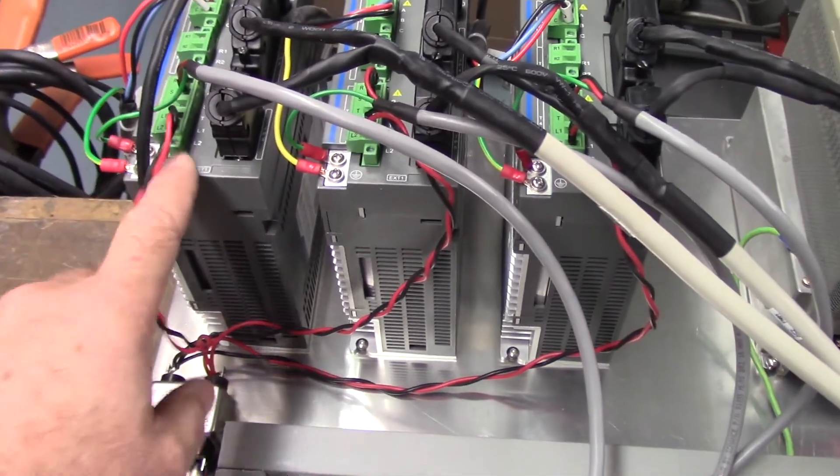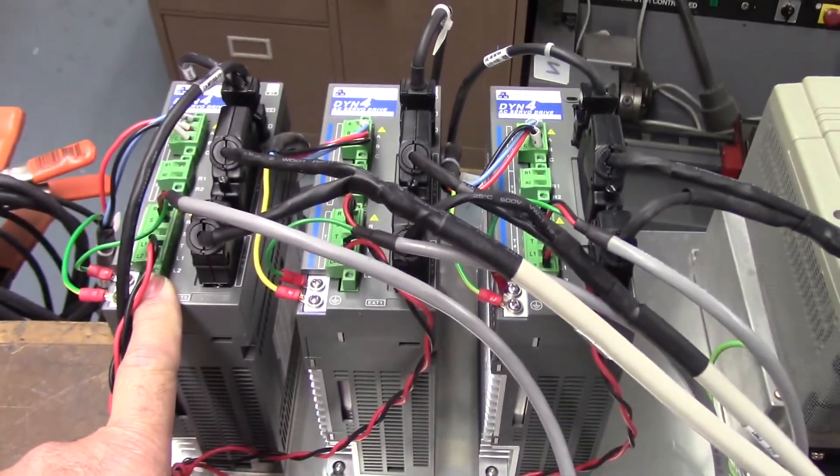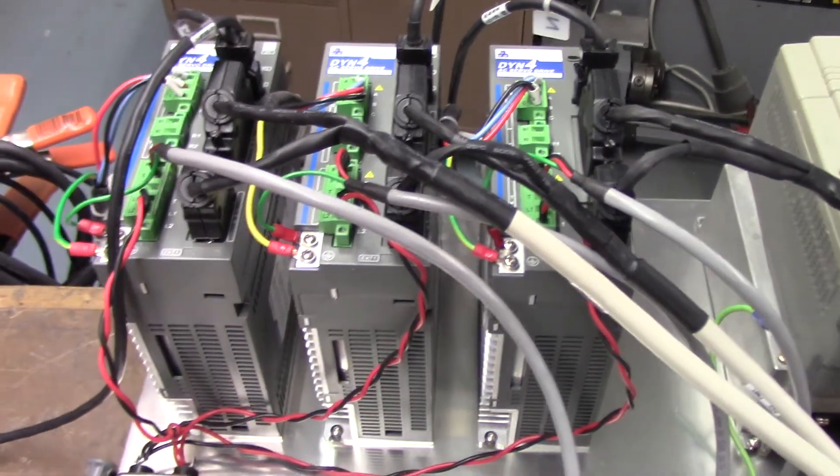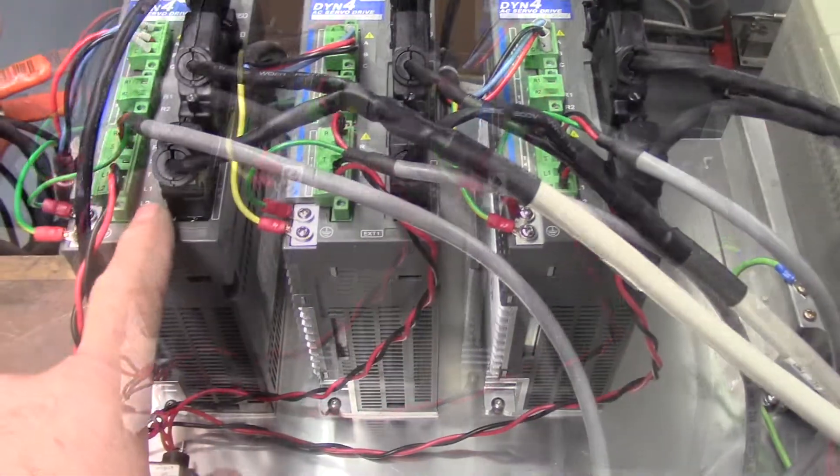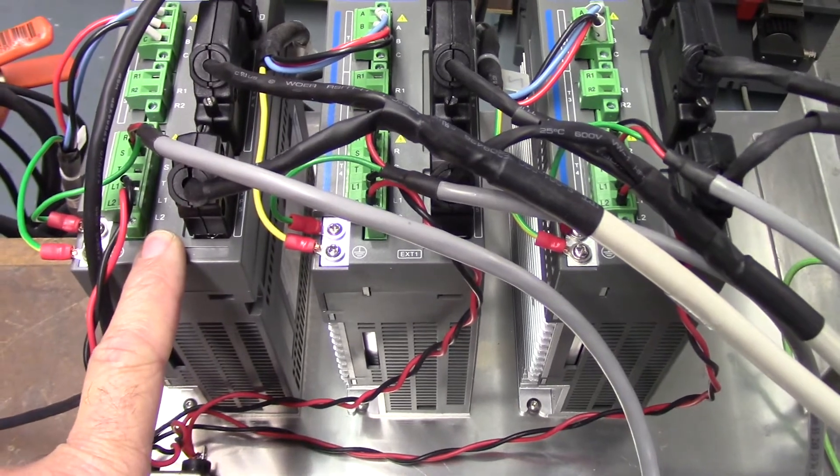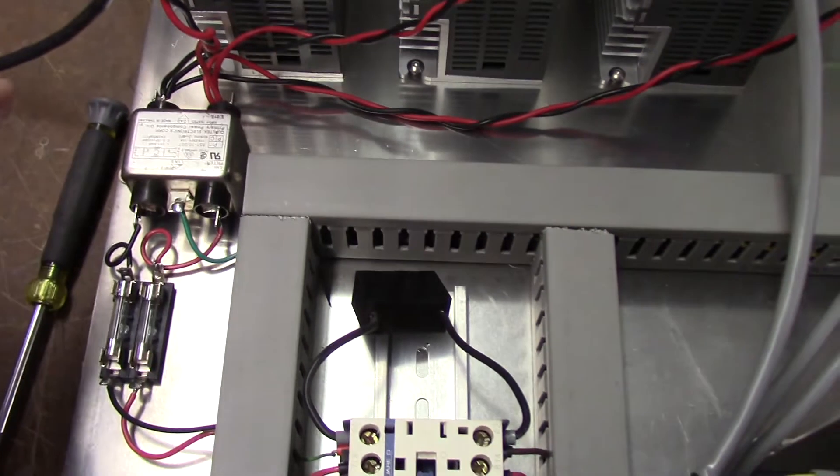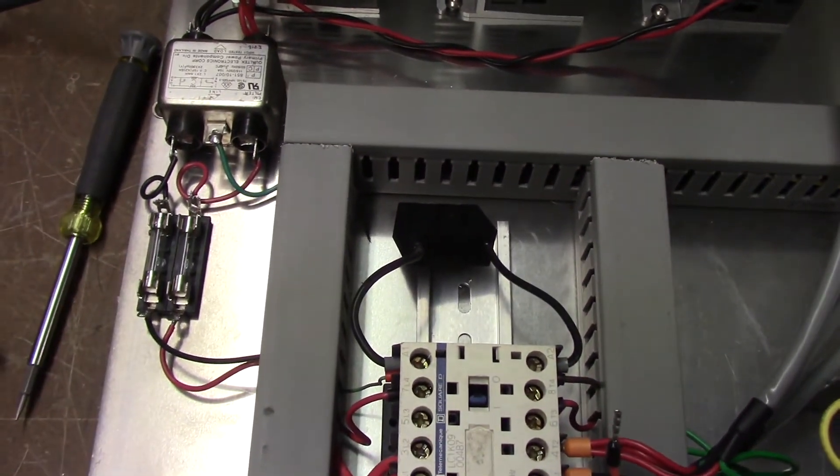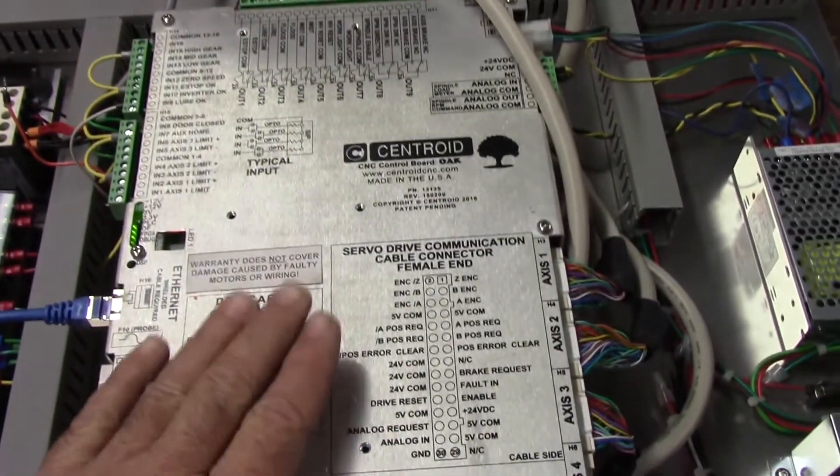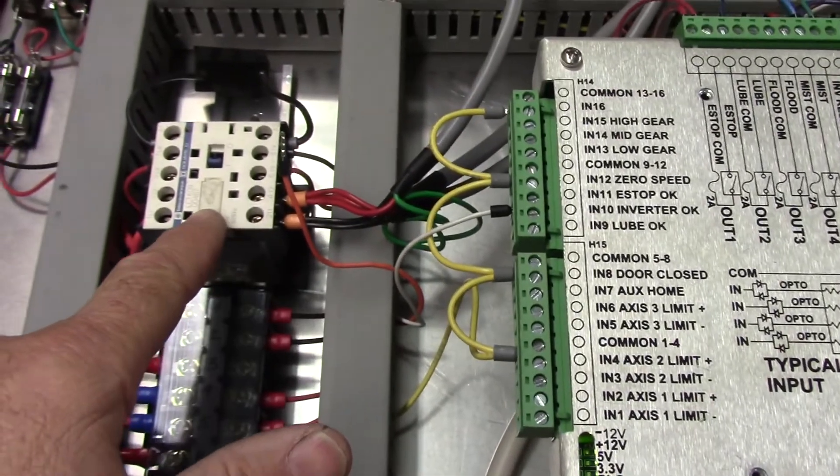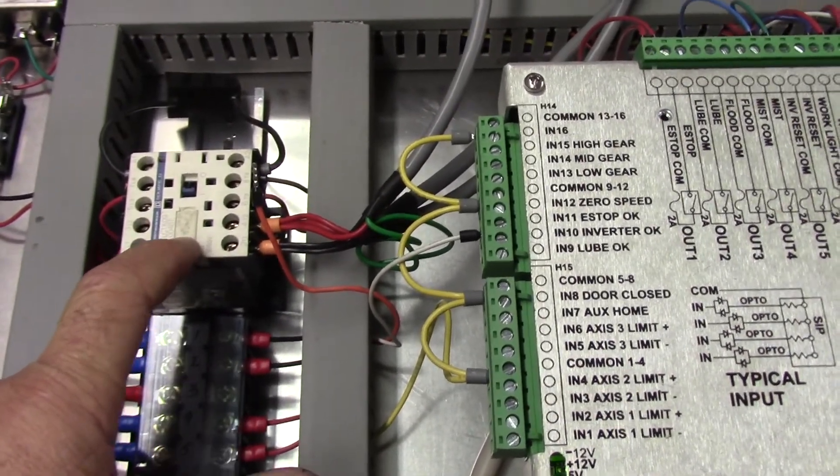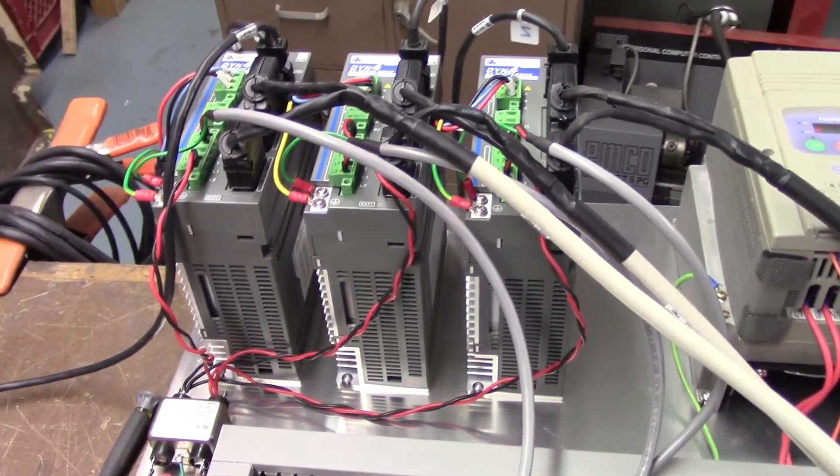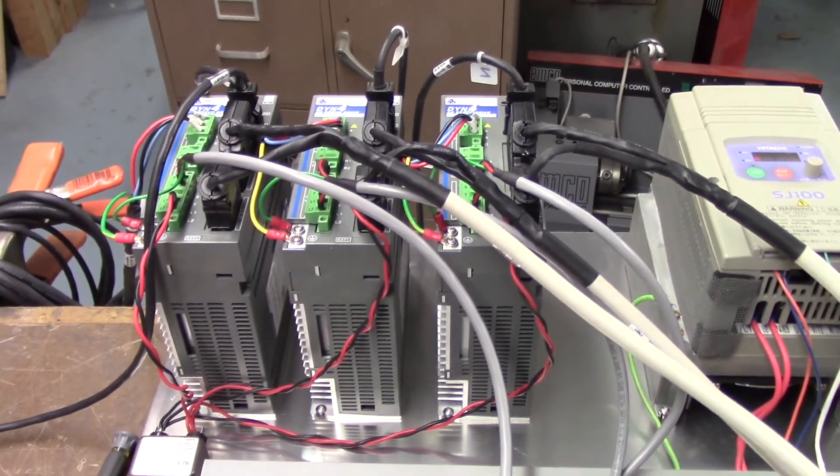These are 240 volt input. DYN4 requires 240 volt input on this particular setup. You'll see that L1 and L2 is logic power, and then R and S is motor power. Logic power is coming down to a filter here and then through a pair of fuses. When the control comes up, that is energized, so logic power is applied at the same time as Oak gets its power, and that's important. Motor power is coming down and going through an E-stop contactor, and this contactor does not close and apply 240 volts to the drives until CNC12 tells it to do so.